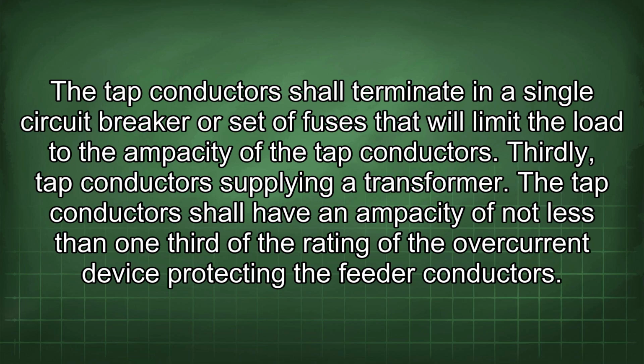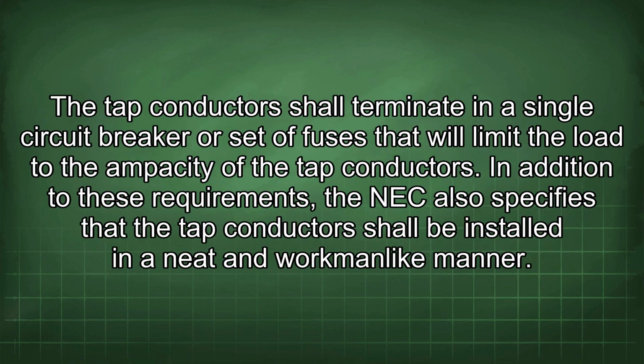Thirdly, tap conductors supplying a transformer. The tap conductors shall have an ampacity of not less than 1/3 of the rating of the overcurrent device protecting the feeder conductors. The tap conductors shall terminate in a single circuit breaker or set of fuses that will limit the load to the ampacity of the tap conductors.